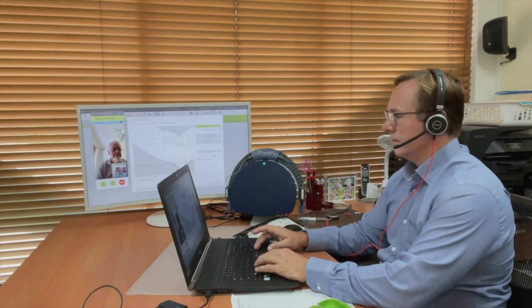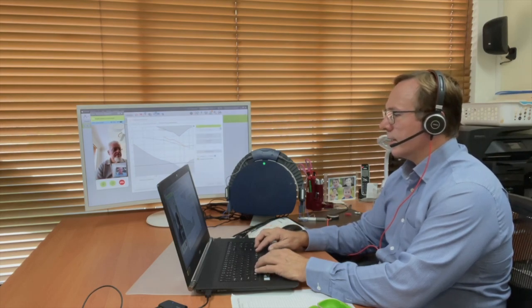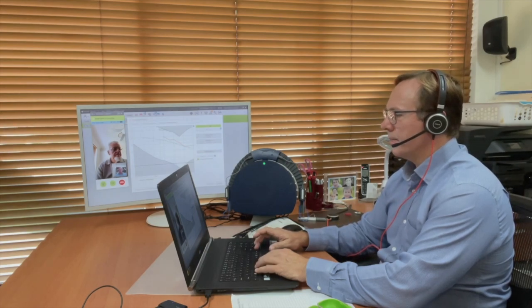One of the reasons this is a more accurate way of programming hearing aids is that there's no coupler volume differences. The acoustic coupling volume of the hearing aid dome is identical to the coupling producing the beneficial amplification in his ears, whereas headphone tests have a much larger volume when coupled to the ear. This coupling volume difference can result in different measurements of hearing thresholds.